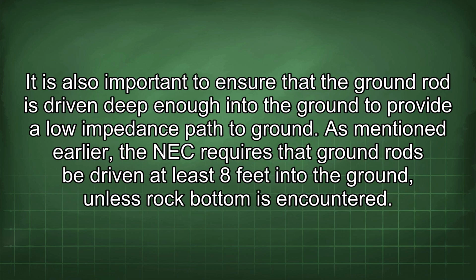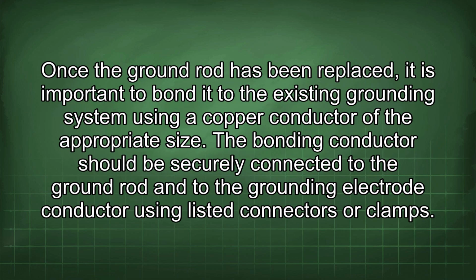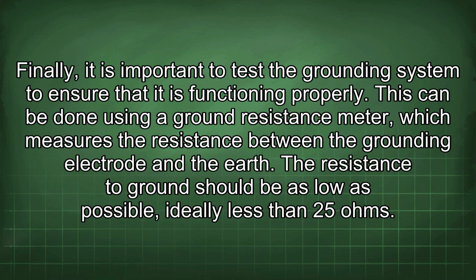It is also important to ensure that the ground rod is driven deep enough into the ground to provide a low impedance path to ground. As mentioned earlier, the NEC requires that ground rods be driven at least 8 feet into the ground, unless rock bottom is encountered. Once the ground rod has been replaced, it is important to bond it to the existing grounding system using a copper conductor of the appropriate size. The bonding conductor should be securely connected to the ground rod and to the grounding electrode conductor using listed connectors or clamps. Finally, it is important to test the grounding system to ensure that it is functioning properly.